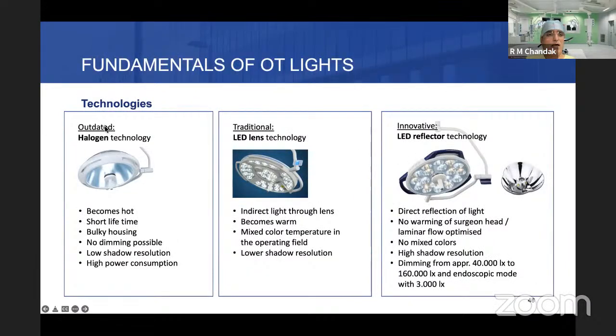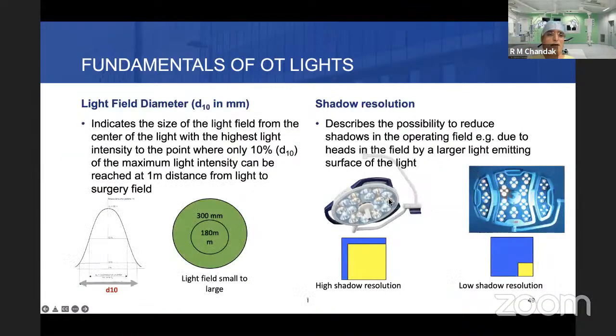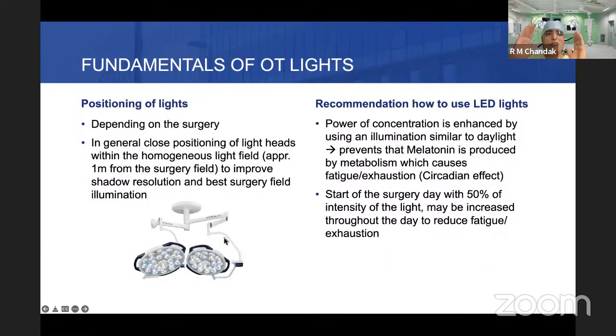The technology, halogen is now almost outdated because the bulb becomes very hot and you have to replace the bulb quite often. During the surgery, they also go away. No dimming is possible, and they have very low shadow resolution. The traditional LED lens technology and the modern LED reflector technology, this is the best, and these are quite compatible with the laminar airflow as well. The light field diameter also has to be looked into when we select the light, and the shadow resolution has to be very good. The positioning of light depends on what type of surgery you are doing.